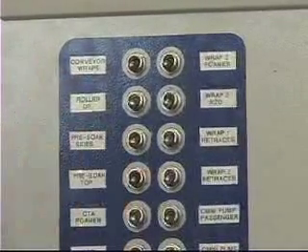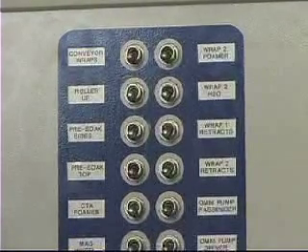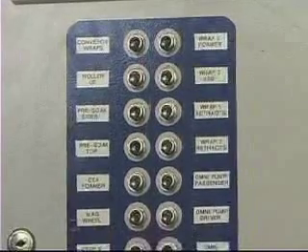Our wraparounds are interlocked to the conveyor, so whenever we start the conveyor up, the wraparounds come on immediately and they're in the retracted position. If the wraparound or the conveyor have a low oil signal sent to them because they have a problem, it'll shut down the entire system.